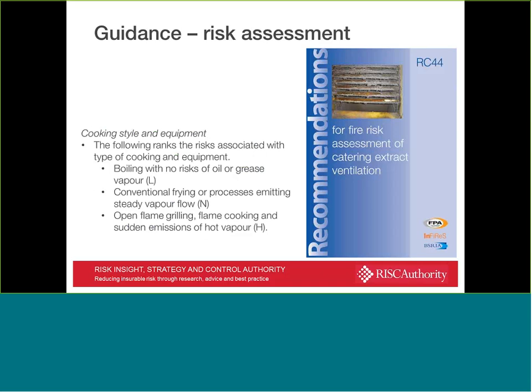But there's no other guidance like it, and I think it's very, very useful in the way that it's laid out itself. So you can see there, if there's boiling with no risks or oil or grease vapor, that's low risk. Conventional frying or processes emitting steady vapor flow can be classed as a normal risk, but if you've got open flame grilling, flame cooking, and sudden emissions of hot vapor, then clearly you're going to see that as a higher risk activity.